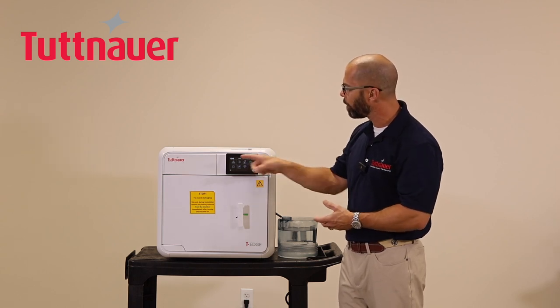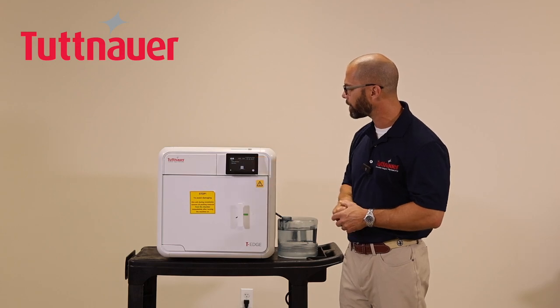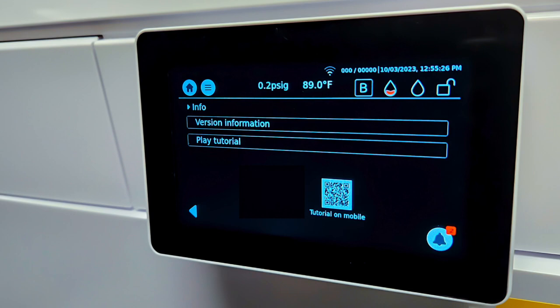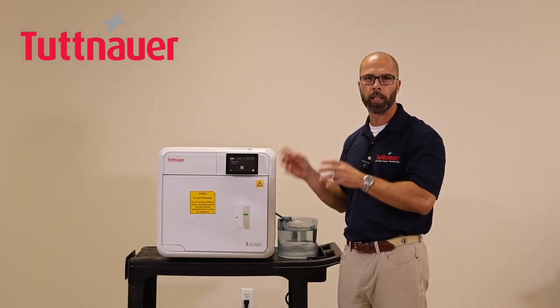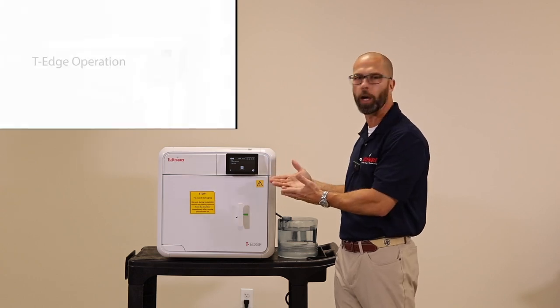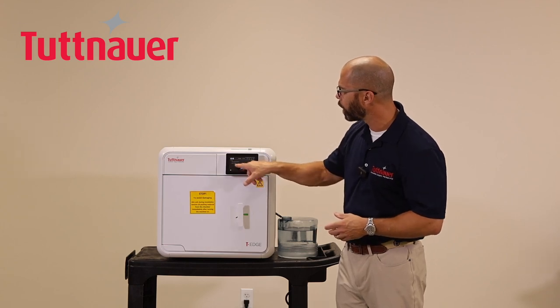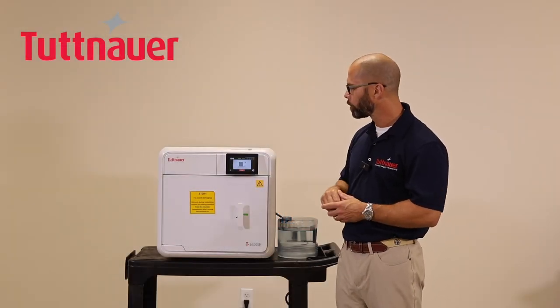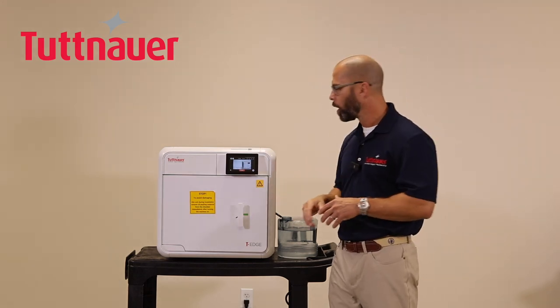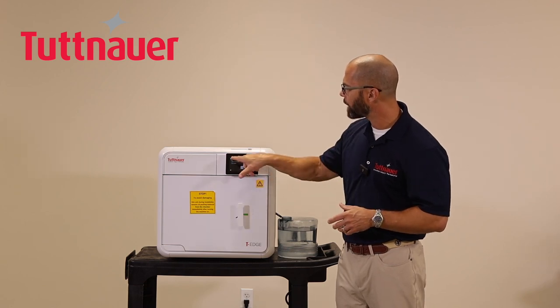One great feature in the dropdown is the 'i' for Information. Press it and you'll see a QR code. Scan that QR code with your phone and it takes you directly to a YouTube page with full audio tutorial instructions. Or you can view the tutorial right on the display — it walks through daily, weekly, monthly, and periodic maintenance without needing to remember any URL. Exit out using the Home button when done.